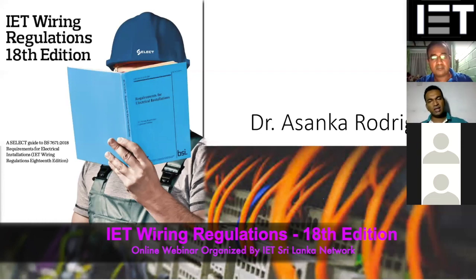But the outside area, because those are coming through the ground, it's like an earthing arrangement, so that if your live wire connects to the earth like that, it should be taken care of by your supply system, the protection arrangement. That is the concept applied in the new regulation.